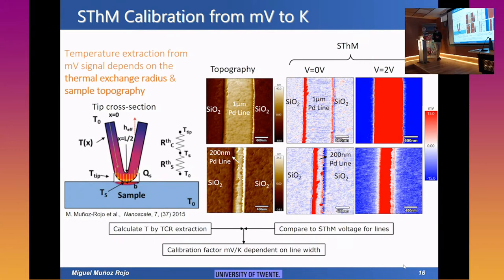So we need to take all this into account. What we decided to do is fabricate different metal lines of palladium, which have a very well-known temperature coefficient of resistance. This allows us to convert, based on the power we apply to the line, what the temperature of the line is. We developed different line widths corresponding to different thermal exchange radii between the probe and the sample, and these also have some topographic artifacts or features between the substrate and the top of the line.